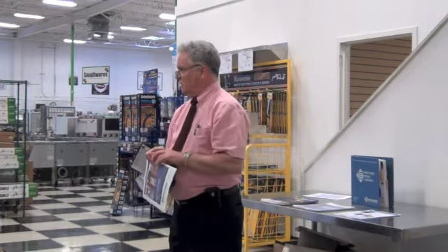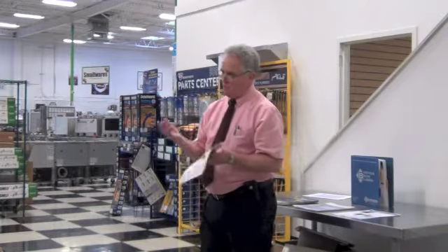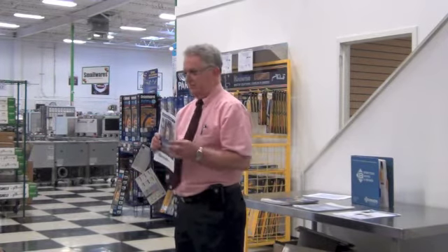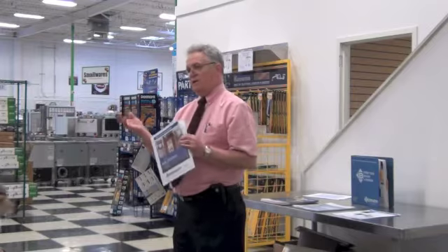What kind of things do you need to know to determine what air curtain the customer needs? Size of the door first. Power source: 120, 208. The price doesn't usually vary by the voltage, but you do need to know it so we wire it correctly. What else do you need to know? What are you using it for? What you're using it for is also a key application, because we're already discussing environment, insects. Those are all key things.